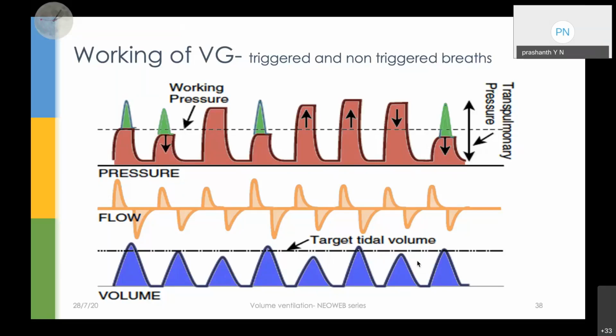If you can see this green, the ventilator is telling us that the baby is actually trying to breathe, your tidal volume is stabilized, and then you see the pressure has increased over here. This feedback will not go to the next breath, because the next breath is a spontaneous breath. This feedback will go to the next breath which has no spontaneous effort. The second feedback of this tidal volume will go to the next spontaneously triggered breath. So it dissociates triggered and non-triggered breaths. Ultimately, your targeted tidal volumes are achieved on a more consistent basis.